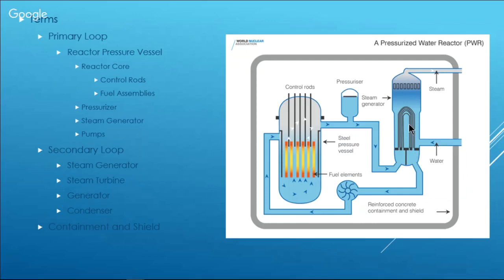And so this goes up, this goes up, and back into the system, and as this goes up, it kind of equalizes out. All you're actually doing is raising the T hot and raising the T cold. When you do that, you increase the T average, because T average is T hot plus T cold divided by 2, so if T hot goes up and T cold goes up, then T average goes up.